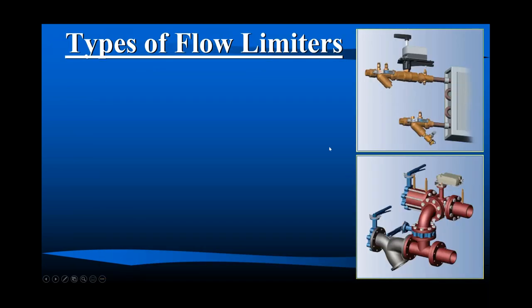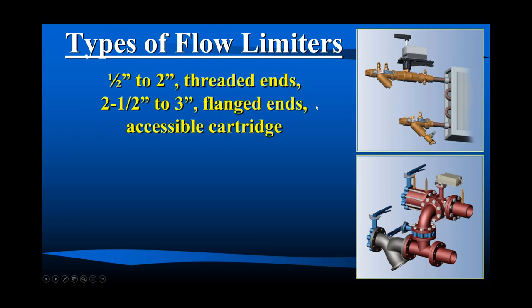Yes, thank you again. So types of flow limiters, again, they're mostly applied at the terminal unit. You don't have to put them on the risers or the runouts. The product involved or sold most of the time is usually up to 2 inch, and this is what it would look like. It usually comes as a kit, if you will, per terminal unit, same valve body. So we always try to put this blowdown down to differentiate the strainer, isolation valve, strainer, blowdown union from this device, which looks like a backward strainer. Again, union as our supply coming back out. Here's our air vent union, control valve union. There's our housing for the cartridge with access verification ports, and lastly, an isolation valve, a true isolation valve. Again, this is not to adjust anything.